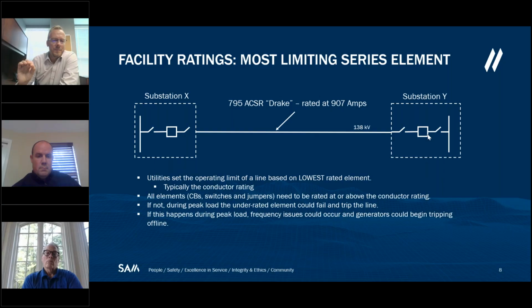So again, the circuit breakers, switches, and the jumpers. Typically, the utility wants to have the main conductor be the most limiting series element. You want your conductor to limit the rating of the facility so that you get maximum current flow across that transmission line and substations. Again, and then the last bullet point is what I mentioned before.